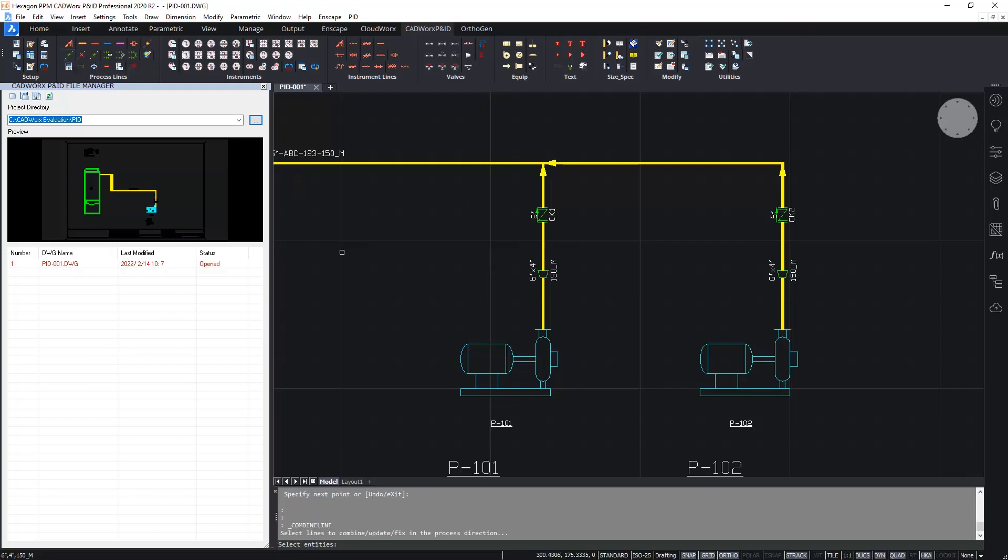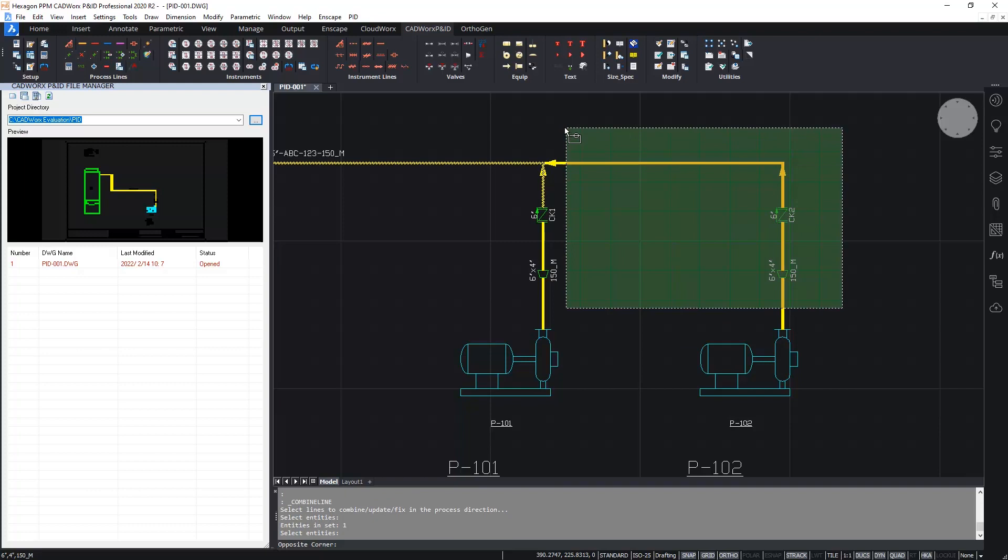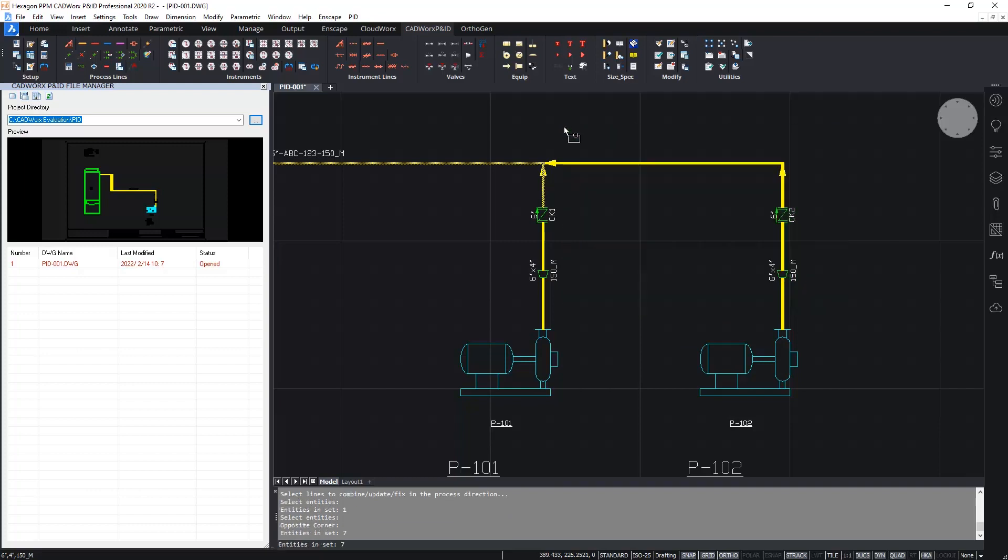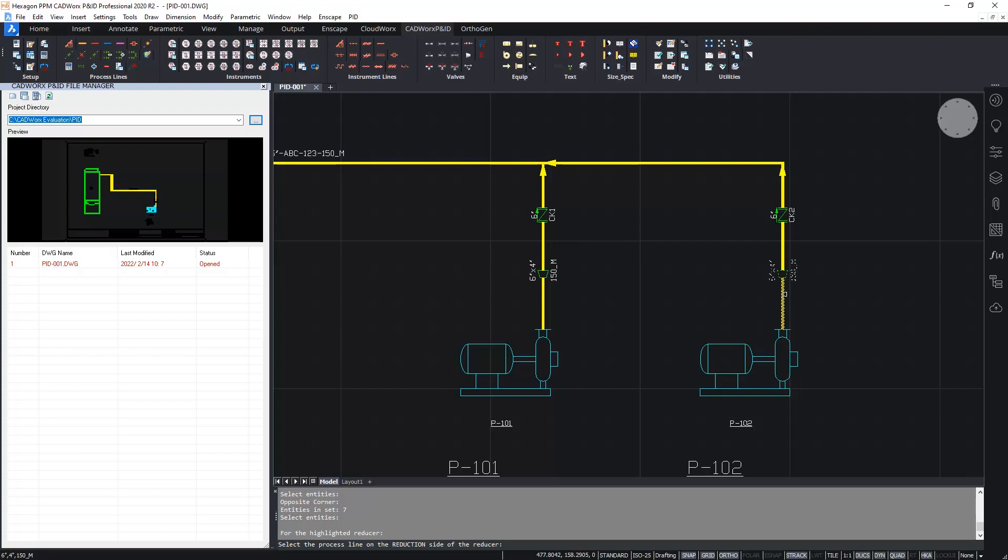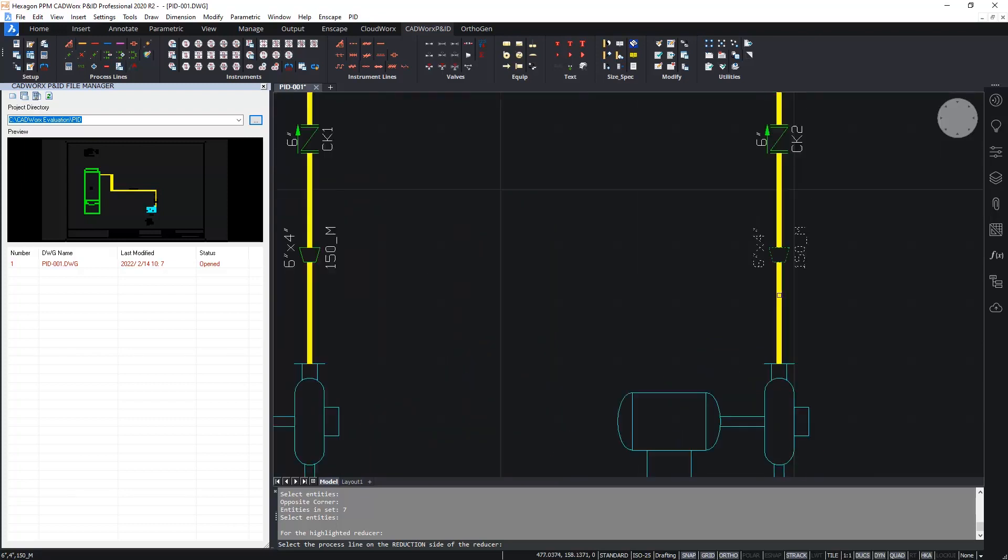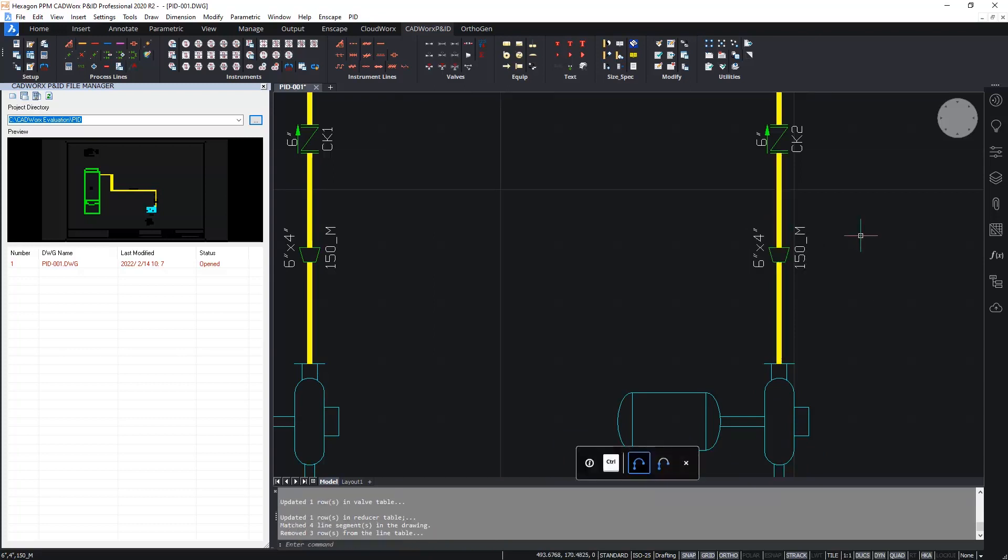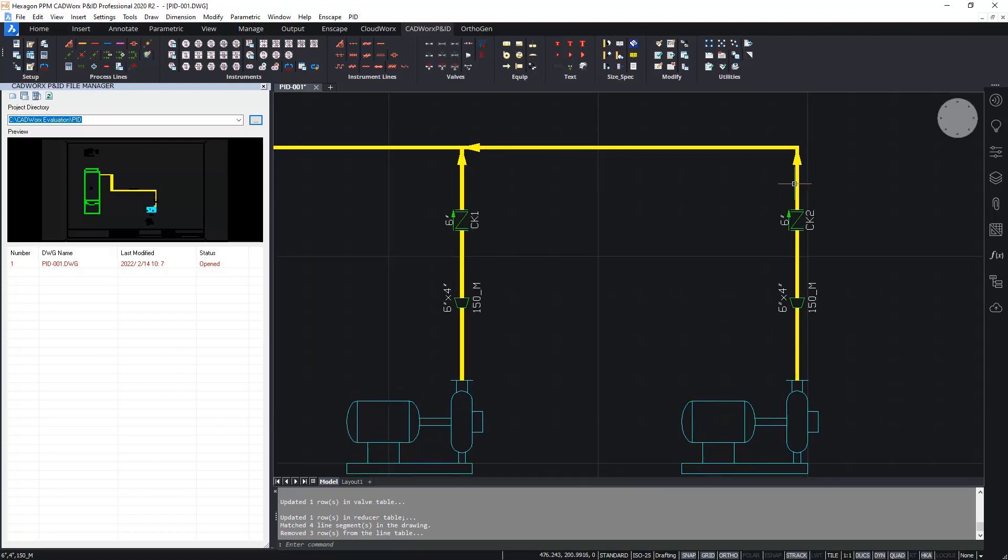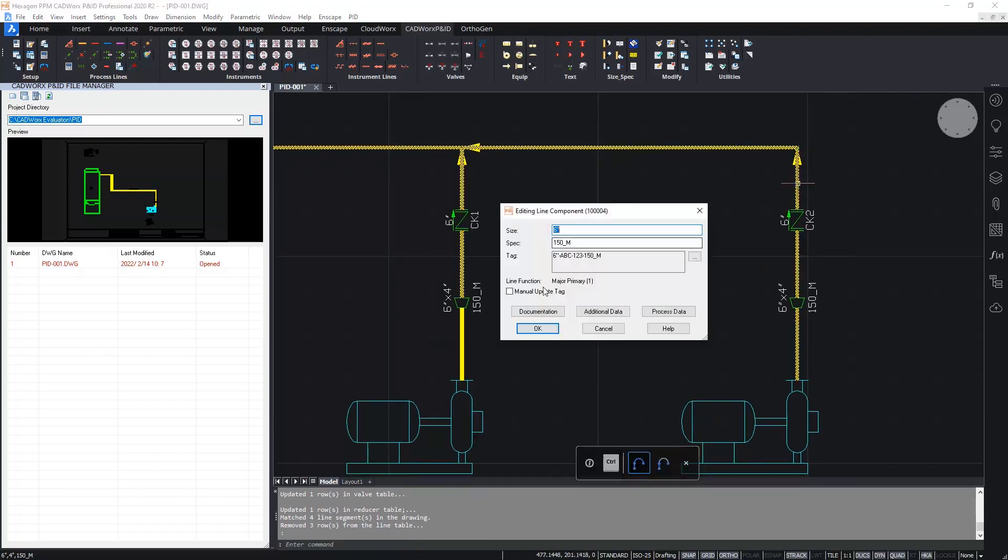So we run combine lines. The first thing to do is select the first process line. And then select the remaining entities to combine, which will be the new items. Because we have a reducer, we need to tell CADWorx which is the reduction side. So I'll select the section of process line on the reduction side of the highlighted reducer. And then the same for the main side of the reducer. And there we have the updated process line now with the correct tag. And as you can see, once I double clicked, all the process line is selected.